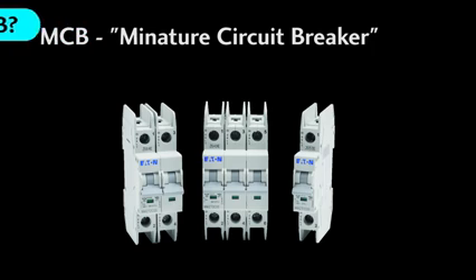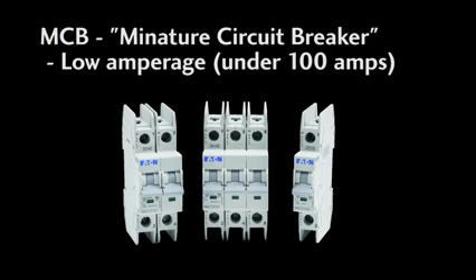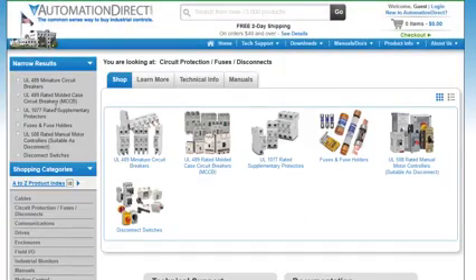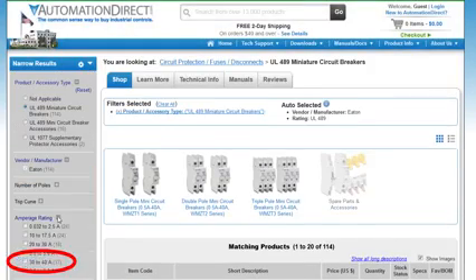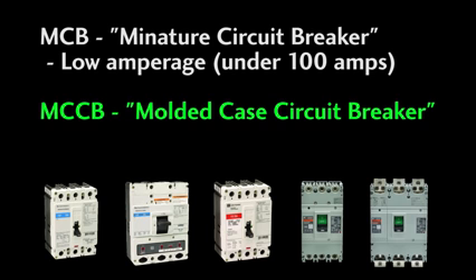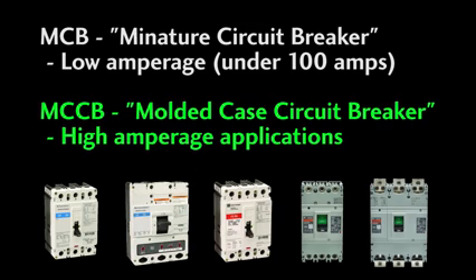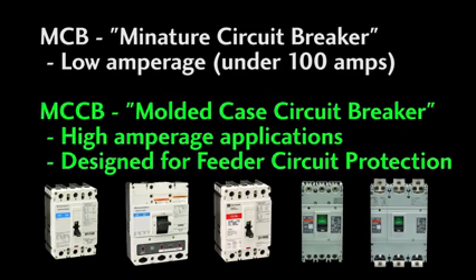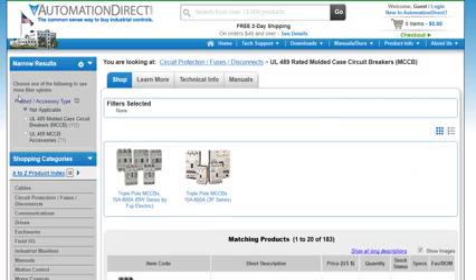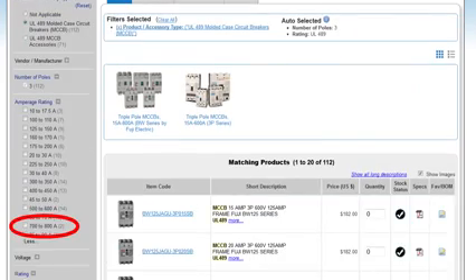MCB stands for miniature circuit breaker, and it's used in low amperage applications on branch circuits in the under tens of amps range. Looks like Automation Direct's MCBs currently go up to 40 amps, for example. MCCB stands for molded case circuit breaker. These can handle over 10 times that amount of current and are designed specifically to meet the requirements for feeder circuit protection. So if you need to protect a feeder circuit, or you have a need for a large amperage branch circuit, you'll want to get an MCCB type breaker. Looks like Automation Direct's MCCBs currently go up to 800 amps.